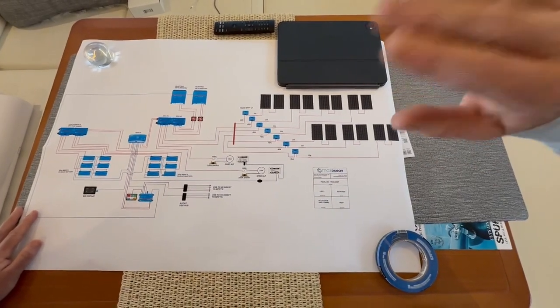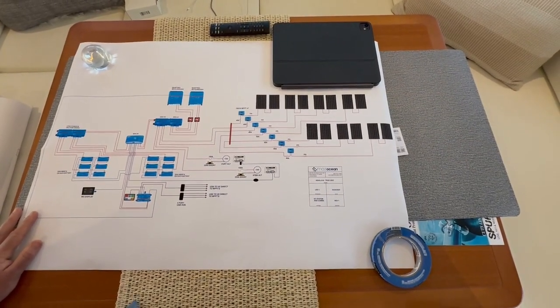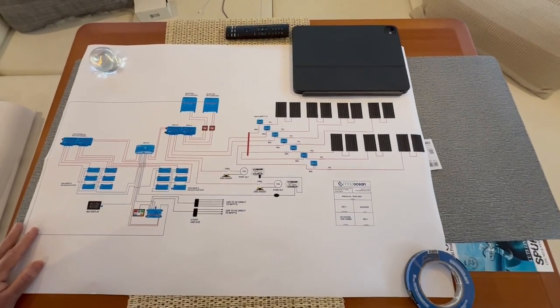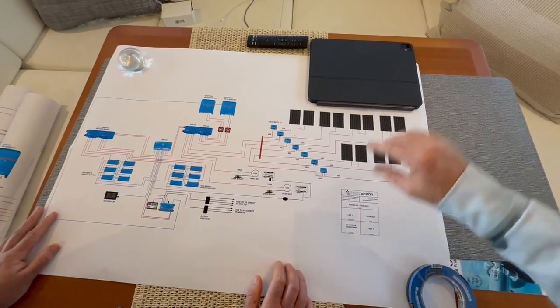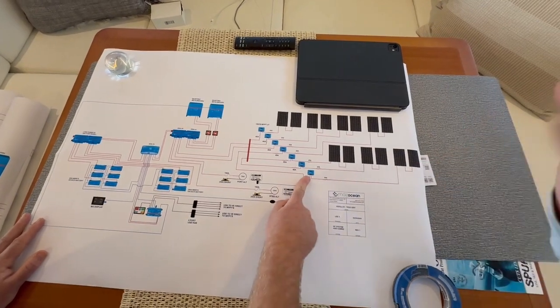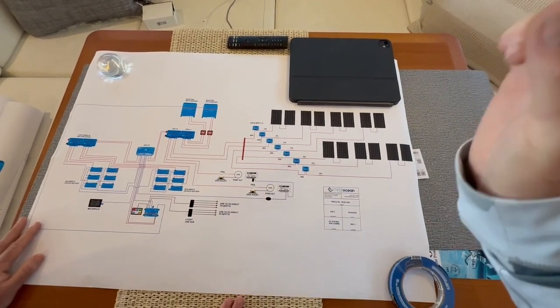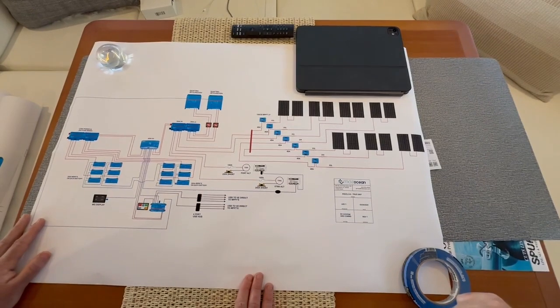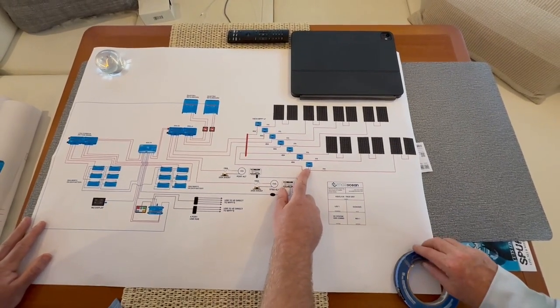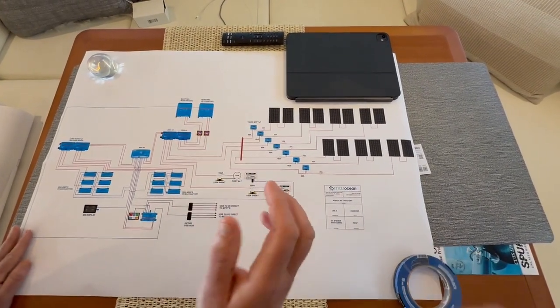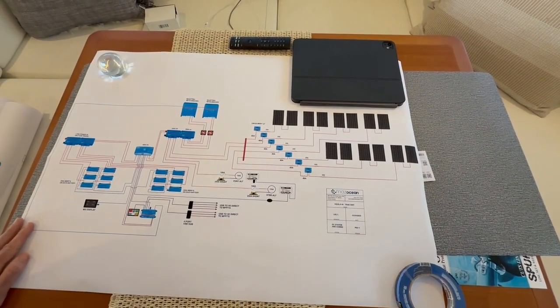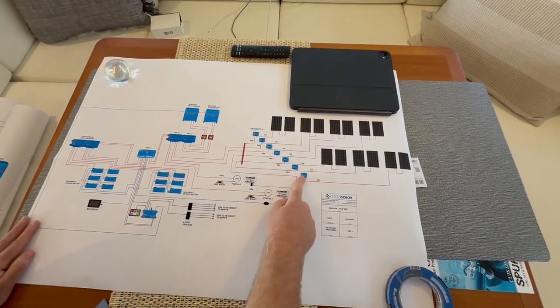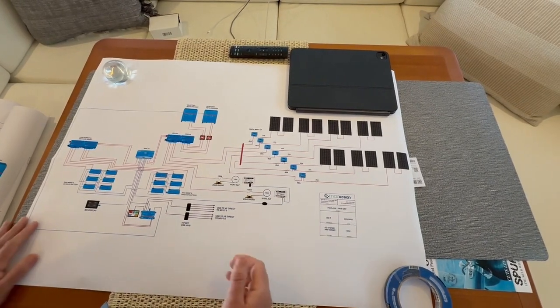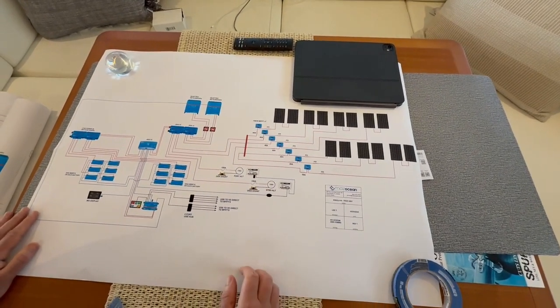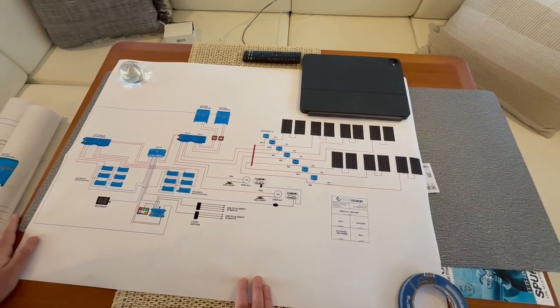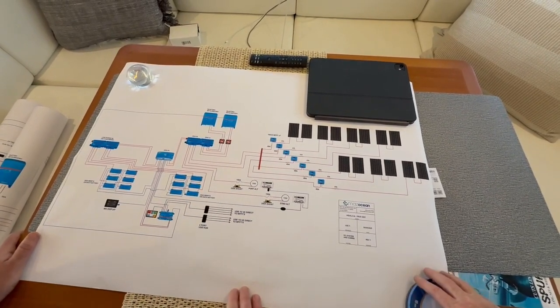What is the service load? Typically about 80% is what you aim towards, or something to that effect. This setup is not overloaded - it's within that sweet spot of production. We didn't want to, say, use a 130 or be right at 95 volts with a 100-volt controller, because if for some reason you went over that 100 volts - a surge or something - you could damage it, or it would shut down and stop operating. So finding that sweet spot of about 80% is generally what you want to be dealing with, load-wise, for generators and similar equipment.